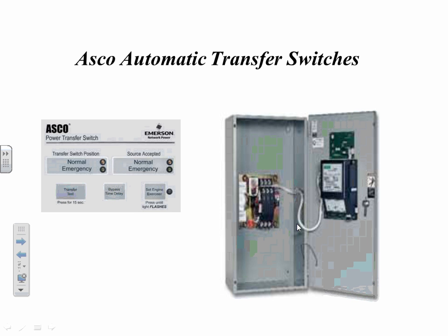This bundle of wires here has those voltage sensors that are watching all the terminals to make sure, especially the utility terminal, is power gone, start the generator set, so the control will handle that. Also, you'll see over here, these are LEDs, these four things here.